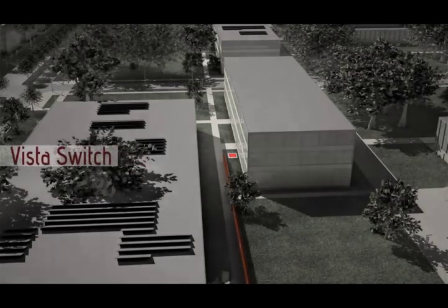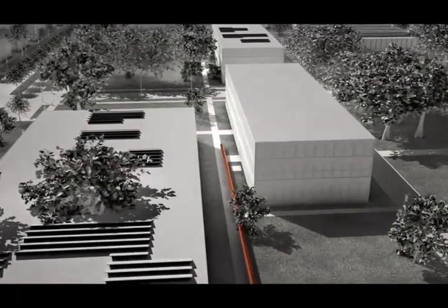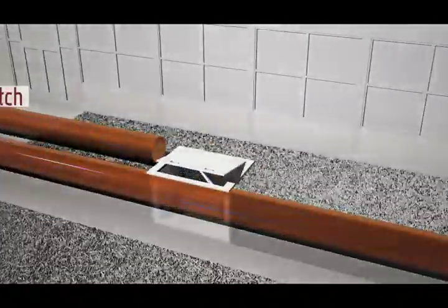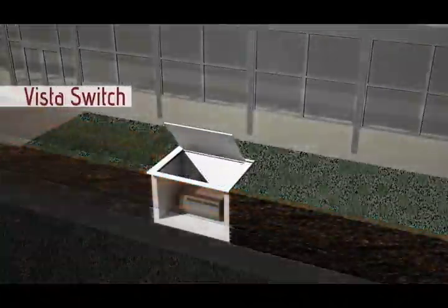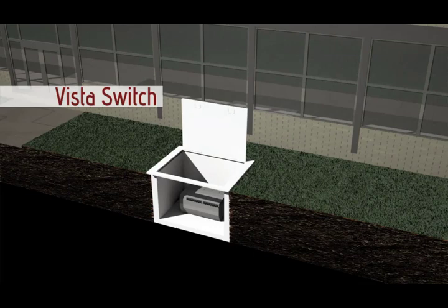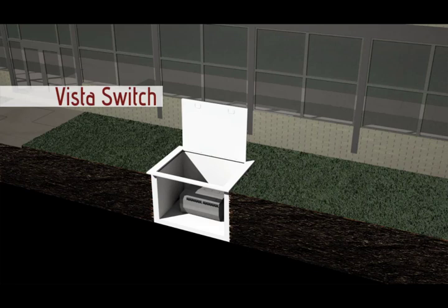Directly behind Siegel Hall is one of three S&C electric VISTA switches. These switches communicate with each other to detect faults in the distribution circuits. If there is a fault, they provide intelligent rerouting of power to keep IIT's buildings up and running while isolating the fault for service and repair.